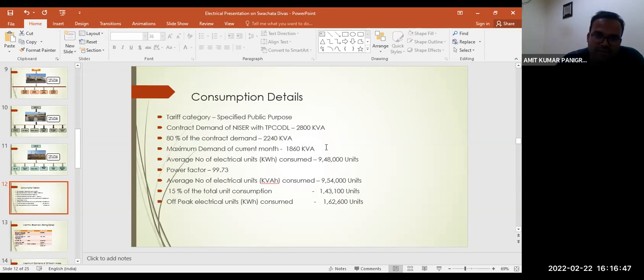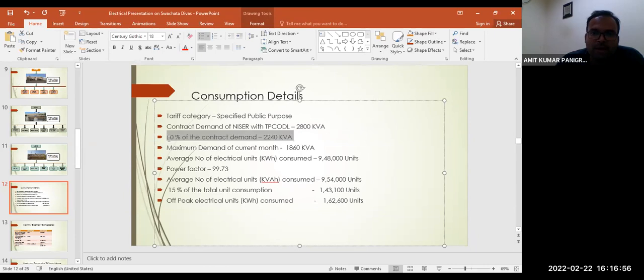If you take more than that, we have to pay a penalty. And if you use less, like in the month of January, we used only 1860 kVA, but we have to pay a minimum of 80% of the contract demand, that is 2240. So even if you use less than 2240, you have to pay the minimum 80% of the contract demand. They put that clause because it is a fixed rate tariff. For supplying a load, they need specific equipment with a fixed cost, like transformers and transmission lines, that you cannot change at your own will. So there is a contract agreement that we will take at most this much. In NISER, the contract demand is 2800. In January, we used 1860 kVA, and it is the monthly fixed cost.